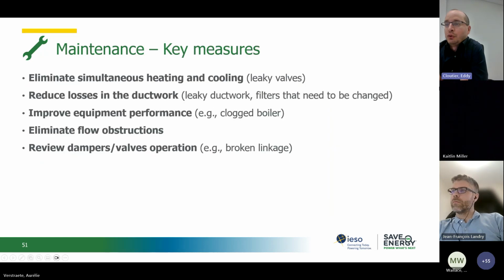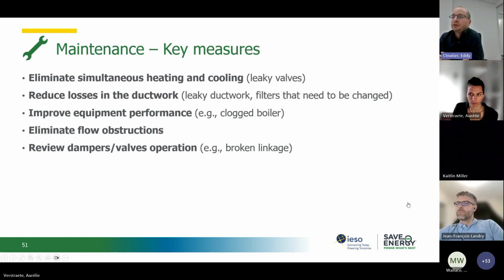Slide. So, a quick summary of the types of measures that could be classified as maintenance measures: eliminate simultaneous heating and cooling, reduce losses in the ductwork, such as leaky ductwork, filters that need to be changed, etc. Improve equipment performance, eliminate flow obstruction, and review damper and valve operation.